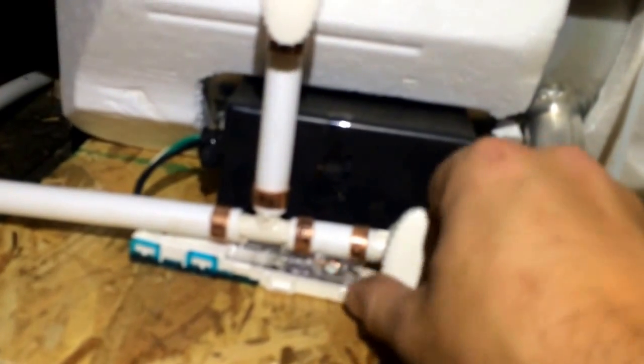Now after winter, springtime — it's time for spring travel. Open this valve, the cold, then you open the top which is the hot. This is the intake, this is the outtake. And then you close the bypass valve. If you don't close this bypass valve, you'll find that you'll have lukewarm water. Some people will say their water is lukewarm, and it's because this bypass valve is open, allowing cold and hot water to mix together. So you want to make sure it's closed.